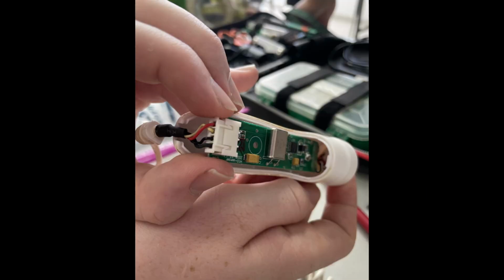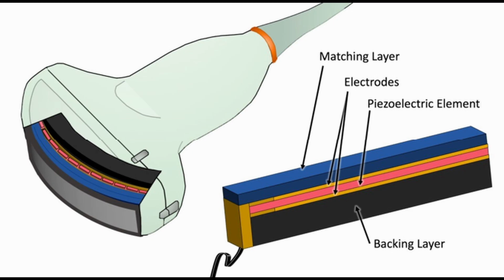A common source of error for these devices is the probe itself, which contains 1 to 2 piezoelectric transducers used for measuring and thus must be handled with care. Issues with the probe may be indicative of issues with the piezoelectric transducer component, which can occur from dropping or extended use of the device. If the issue is narrowed down to the piezoelectric transducer, they may need to be replaced to make the device functional again. Replacement of the transducers may outweigh the cost or the value of the device in total.